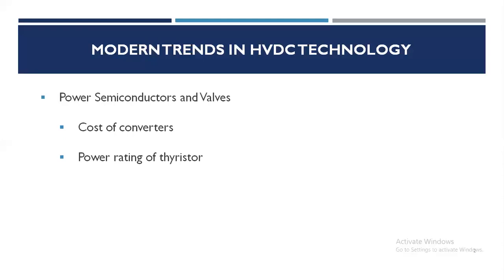The power rating of a 12 pulse converter unit has increased up to 3000 megawatt at 500 kilovolt. LTT, that is light triggered thyristor valves, rated at 125 kV, 2400 ampere are used at Sakuma frequency converter station in Japan. LTT valves rated at 133 kV, 2000 ampere have been in operation in the Celilo converter station of the 500 kV Pacific Intertie system in USA since 1997. Each valve is made up of 44 series connected thyristors arranged in two modules.